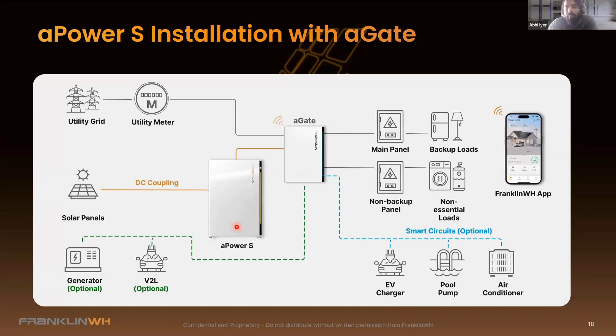For the designers in the room, this is what a single line diagram of the aPower S looks like. PV is landed through the specific RSD transmitter kit onto the aPower S, and the output of the aPower S is then landed on the ESS breaker on the aGate, rated for 60 amps.